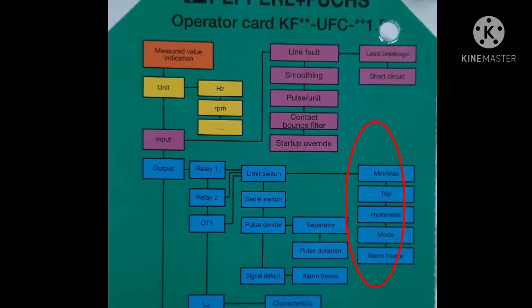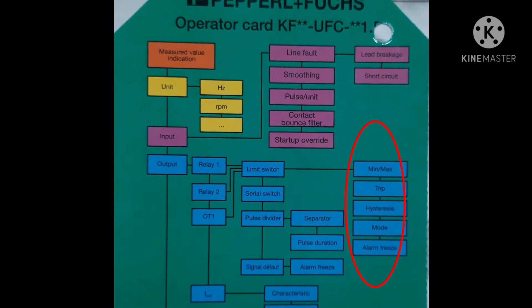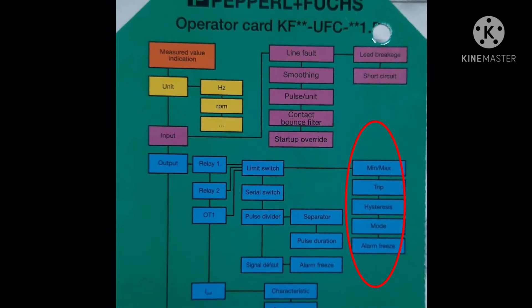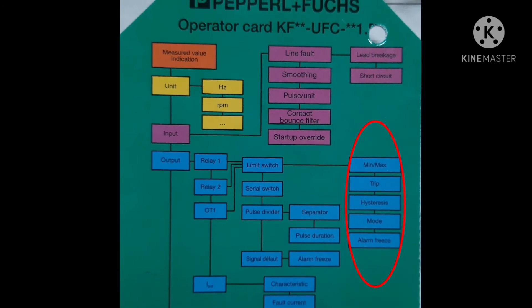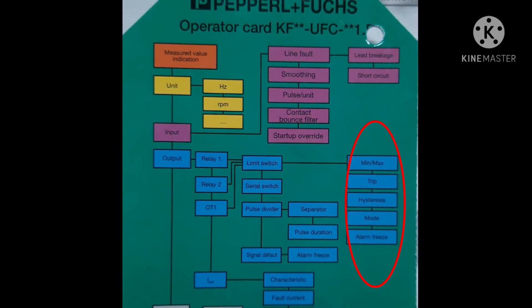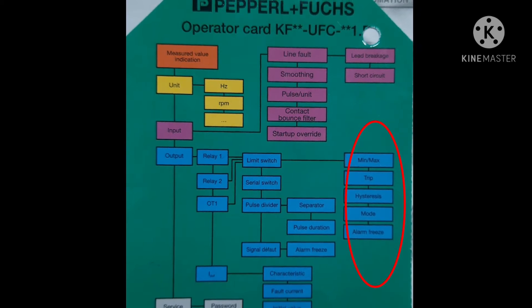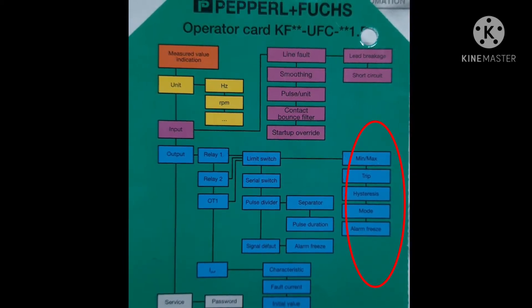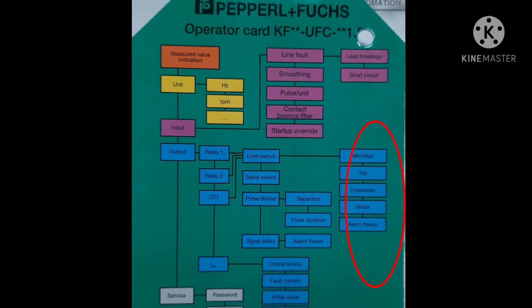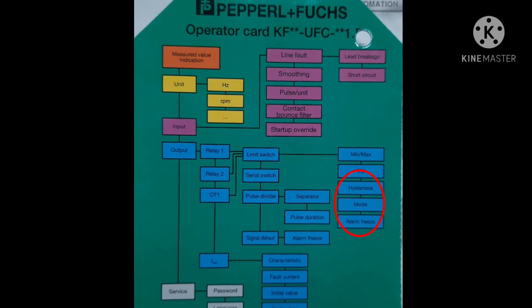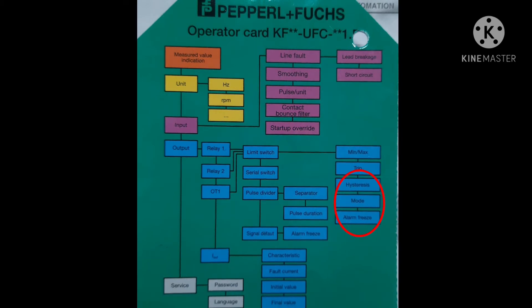For min/max, select 'max' and press OK. Now you can see your window shows 'trip'. Go ahead and write the tripping speed, which will be 125% of your generator speed, then press OK. The window will show 'hysteresis' — go ahead and write 10% of the 125% generator speed value.